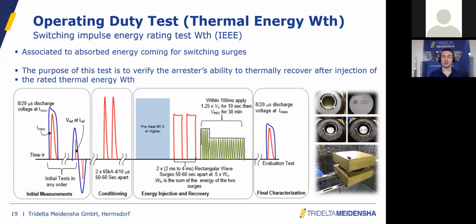To make it simple, this test is done on an MOV section, which very often means 2 MOVs plus the housing, and the housing is important for the thermal behavior. The idea is to pre-stress the block with some high current impulses and preheat at 60 degrees. Then you inject the required energy, WTH. After injecting the energy, you apply the rated voltage, which is like a temporary overvoltage, for 10 seconds. Then you apply the continuous operating voltage for 30 minutes, and you want to make sure that the temperature decreases and comes back to the initial values. Then you perform some tests on the block to make sure that they have not lost their initial characteristic.